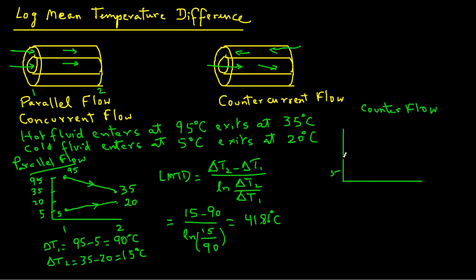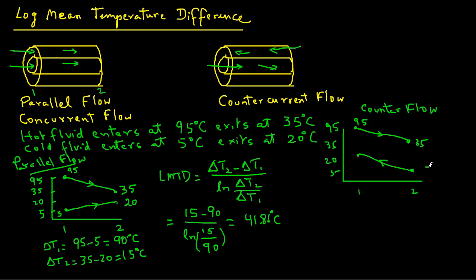Again, we draw the axes: Y-axis for temperature, X-axis for locations 1 and 2. The temperatures are 5, 20, 35, and 95. The hot fluid enters the counter-flow heat exchanger at 95°C and exits at 35°C. Because this is counter flow, the cold fluid enters at location 2 at 5°C and increases to 20°C. So delta T1 is 95 minus 20 = 75°C, and delta T2 is 35 minus 5 = 30°C.